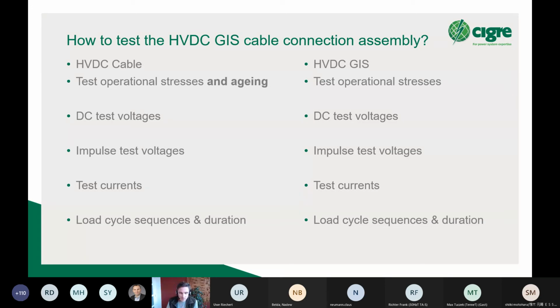And this means that there are different load cycle sequences and durations. The DC test voltages in the cable tests are generally higher than in the GIS tests. The impulse test voltages for the GIS are higher than those for the cable, and the test currents used in the HVDC GIS are also higher than those used in the cable.